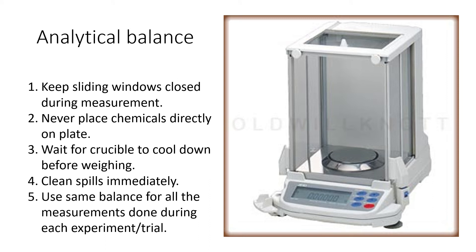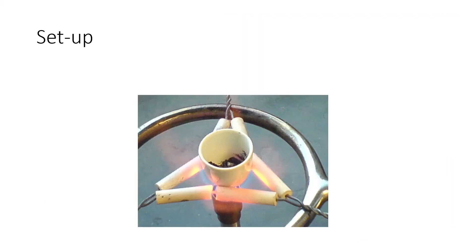Always use the same balance. So once you decide I'm going to use balance, let's say, number one, you have to use the same balance for all the measurements done during each experiment, during each trial of that experiment. The reason is the balance has been calibrated at the position that it is on the bench. If you switch balances, you risk using a balance that is off by maybe a milligram or so, and in these kinds of experiments a milligram or so is quite a difference.